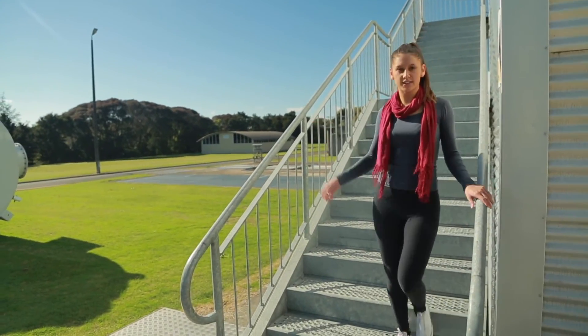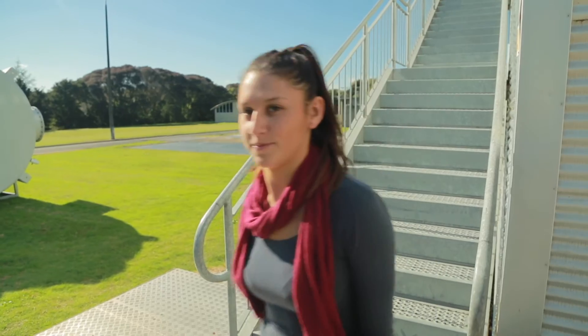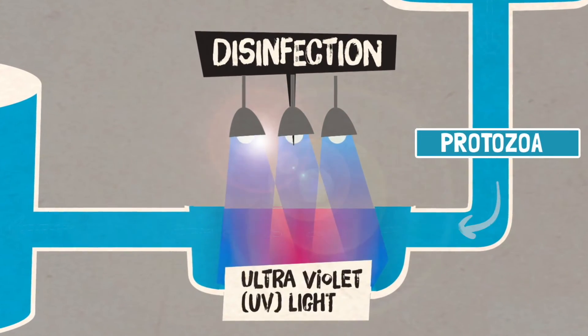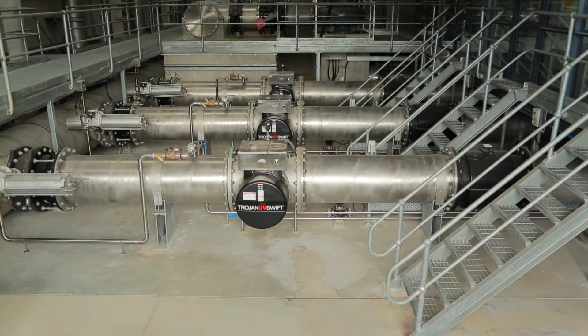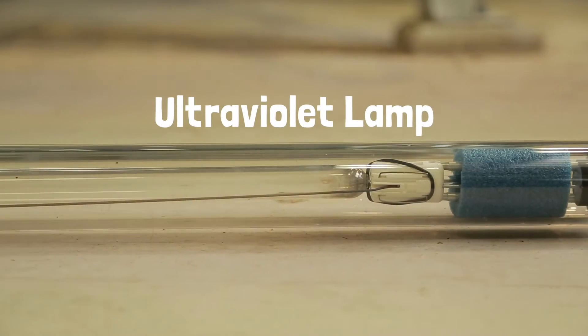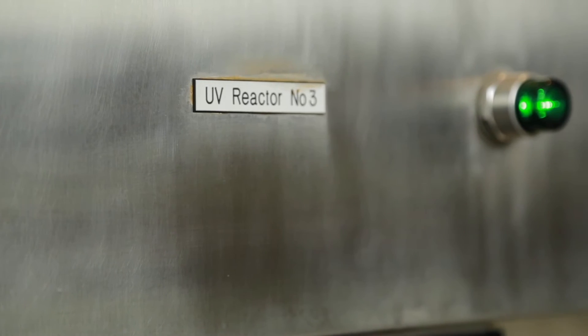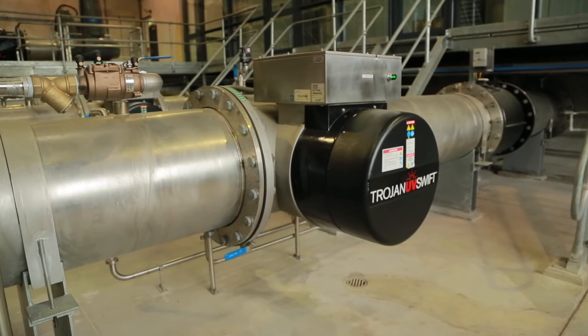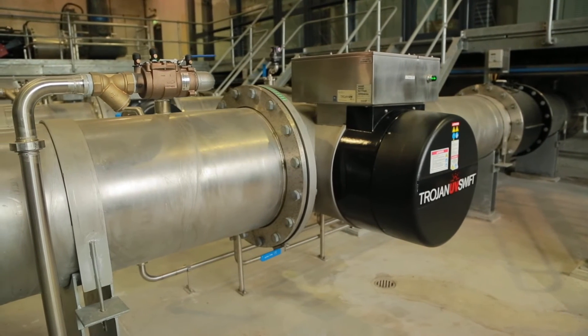I've been walking all over this water treatment plant — surely the water's clean by now. We've dealt with the larger microorganisms, but are there any remaining microorganisms? This is the UV area. These are here to zap any remaining microorganisms, even protozoa, which are single-celled microscopic organisms. The UV light deactivates these organisms by permanently altering their DNA structure, so they are unable to infect or reproduce. Water is passed through these large cylinders filled with UV tubes — and that's where the zapping happens.